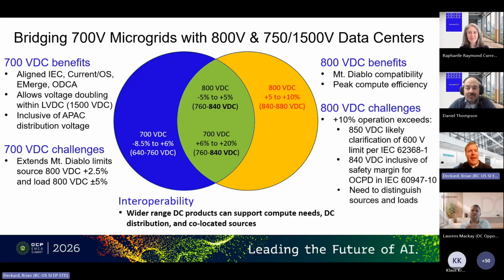As Daniel mentioned, we recently came off some great discussions within OCP EMEA in Barcelona, where we presented a look forward into the future of 800 volts and beyond, with data centers reaching plus/minus 750 volts, or a total of 1500, as well as a look back to the foundations laid for DC microgrids at 700 volts. There's a lot of convergence and alignment between Current OS, Emerge, ODCA, and the existing IEC TR 63282, around standardization of voltage bands, particularly this nominal 700 volts, which, as shown in the blue circle on the left, represents an intersection with the 800 volts being considered in the data center space.